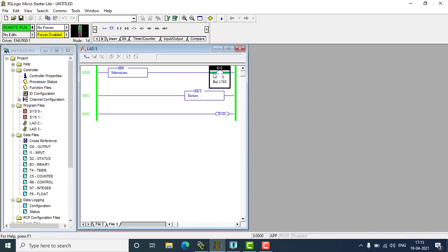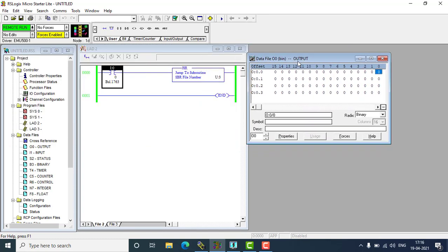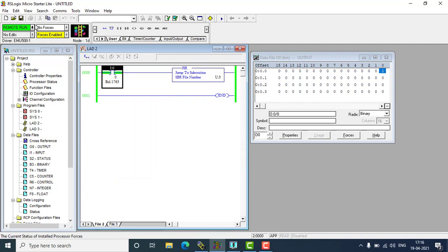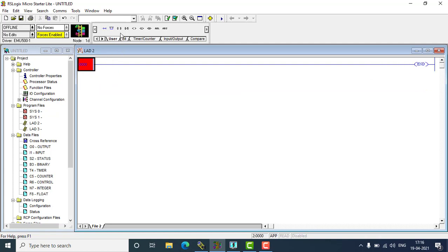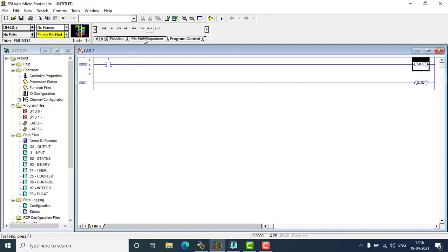Going back to Ladder 2 — if I disable this, you can see in Ladder 3 the output is still prevailing. I have to toggle it off manually. If you want to watch on the output section you can watch it there also — Output 0 will only be enabled when the sub program is enabled. Now I'm going offline and I'm going to show the Master Control Relay. There is one issue with the sub program: when the sub program input is turned off, there is no effect on the output.